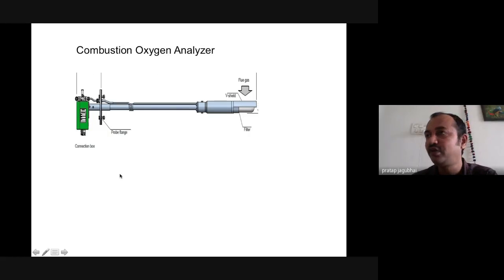Another important instrument for measurement, required for combustion control, is the stack oxygen analyzer. The stack oxygen measurement is basically governed by the Nernst equation, where the logarithm of the partial pressure difference is proportional to the EMF generated at 750 degrees, based on a zirconia analyzer. The zirconia membrane acts very well at 750 degrees temperature, and at this temperature the logarithmic partial pressure difference between the reference air and the flue gas will be proportional to the stack oxygen actually leaving the furnace. So that will give you the indication of the stack oxygen leaving the furnace.